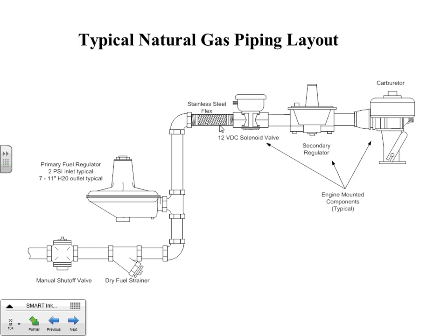Comes around, and anything connected to an engine generator is going to have flex, even the gas line. So we've got a stainless steel braided flex section here, and that's because the engine rocks when it starts, and it's going to move some. And these three components are typically engine mounted. Got a, I said 12 volt DC solenoid valve, and that's going to be activated from the start signal on the generator. It's going to click not only to start cranking, but also open up this valve to allow the fuel to start to flow. The secondary regulator here, which knocks down the pressure a little more and then feeds it right into the carburetor.